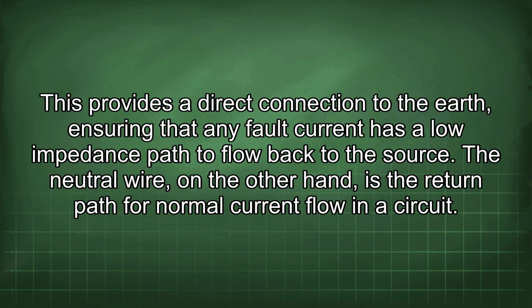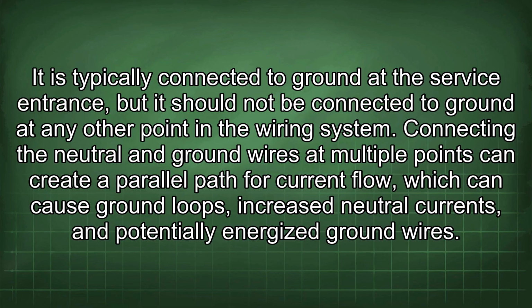back to the source. The neutral wire, on the other hand, is the return path for normal current flow in a circuit. It is typically connected to ground at the service entrance, but it should not be connected to ground at any other point in the wiring system. Connecting the neutral and ground wires at multiple points can create a parallel path for current flow, which can cause ground loops, increase neutral currents, and potentially energize ground wires.